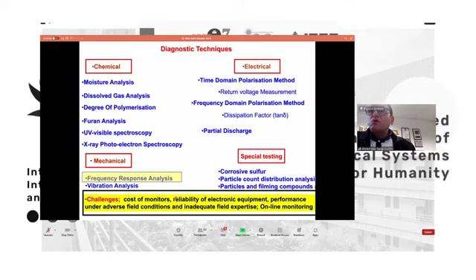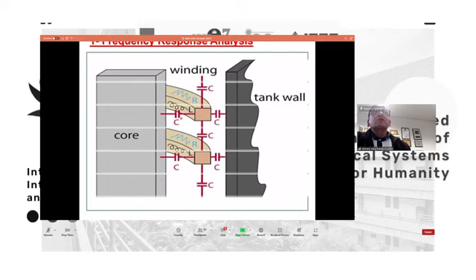So back to the principle, we know that the power transformer, including the core, winding, and insulation system, can be represented by an equivalent electrical circuit. This circuit comprises resistive and inductive components, representing the main winding, which is copper or aluminum, and the insulation system, which is paper and oil, represented by a capacitor and conductance. So that's the equivalent circuit of the transformer in the high frequency domain. That's one disk or one turn only. I put some animation here just to follow me.